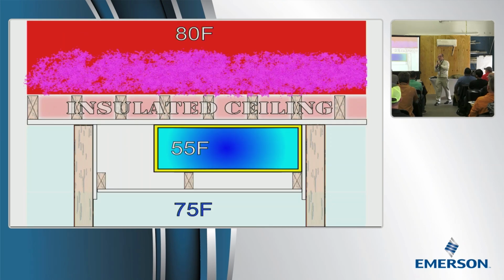What about ducts that are in the conditioned space? That's one way to do it. If you don't want to foam and create a dry, low dew point space up above your ceiling, then one of the things that's done is, well, I'm going to have a vented assembly above the ceiling, but I'm just going to put all the ductwork below it. Good plan. Excellent plan. In other words, I've got a vented attic, I just don't put ducts in it, and I certainly don't put an air handler in it. That's a good plan. That's not a bad way to build a building.